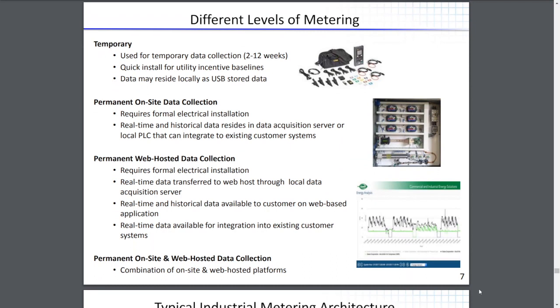So there are a few different levels of metering, just to review. Temporary metering is a great first step—it goes in quickly, it's usually the first solution, and sometimes it's the only one needed. Take a lighting project, for example: you might change a couple hundred bulbs, metering for a couple of weeks before and after the change. Once the project is done, the lighting runs the same as before, just at a different level, so there's no need for ongoing metering—that's a good argument for temporary metering. For longer-term projects where conditions may change and you want to keep watching loads, permanent metering is the next best step. The downside is it requires a more formal installation and takes longer to become operational.